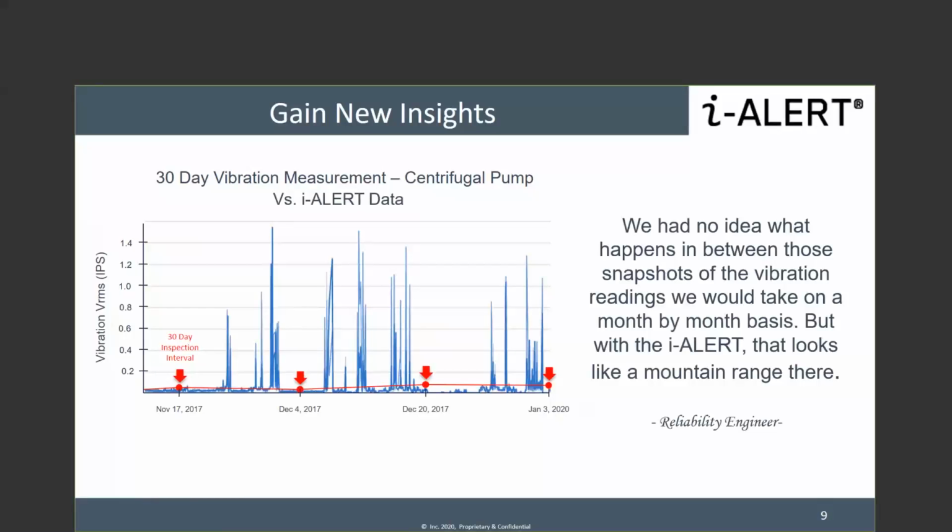This particular case is a real use case where an equipment's seal kept failing, and they really did not know what the issue behind it was. So they put an iAlert on there, started trending the data and collecting it periodically, and saw that between B and C shifts, the valve wasn't closed and it was dry running. That's what we're trying to let our customers know: at the end of the day, if there's a mechanical fault, you can run it against the diagnostic rules engine. But if there is a process issue, you'll also be able to catch that using a trending tool. Like I mentioned, we're trying to give you a full-fledged solution with everything we can think of that can fill in the gaps, right?